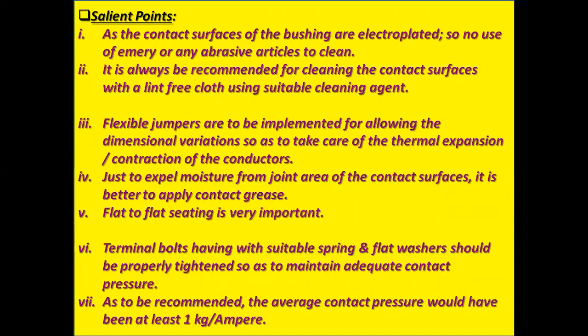Salient points. Number 1. As the contact surfaces of the bushing are electroplated, there must be no use of emery paper or any abrasive articles to clean the contacts. You must remember these salient points. Number 2, it is always recommended to clean the contact surfaces with a lint-free cloth using a suitable cleaning agent.